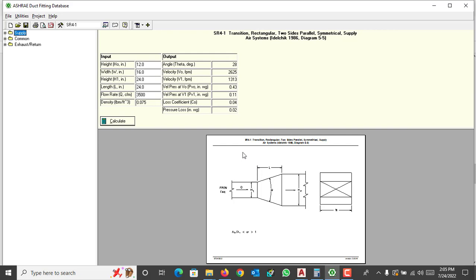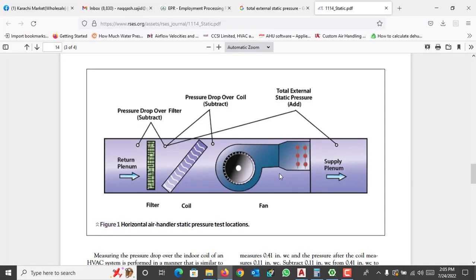Today we will discuss external static pressure: what is external static pressure and what is total external static pressure — both are different. External static pressure is actually the pressure that overcomes the losses in a duct. It may be a straight duct, fittings like elbows, reducers, transitions, bell mouths, and different registers and VCDs connected with the duct — all come under external static pressure.